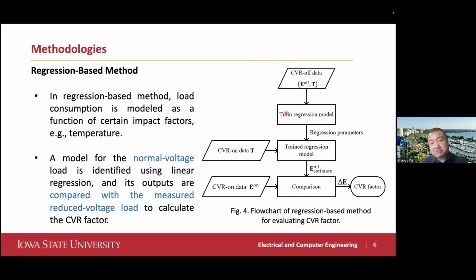Another method is a regression-based method. This is very commonly used by a lot of utilities here in the United States to evaluate their CVR factor. It's actually pretty simple, like load forecasting. They model the load as a function of temperature and also as a function of CVR on and off, then use normal voltage data to do the regression, so that you see how this load is correlated with voltage, with temperature, and also with CVR status.